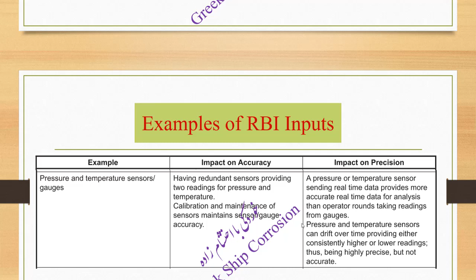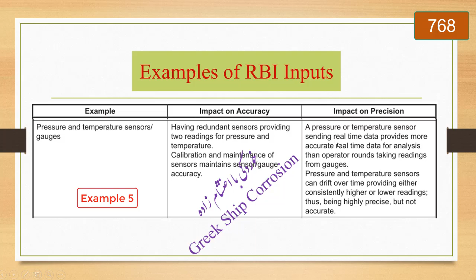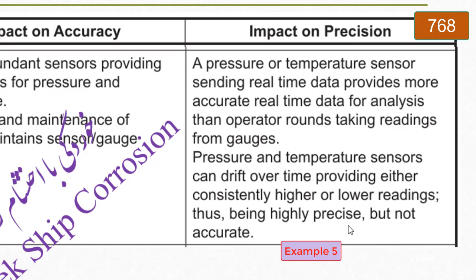Another example, pressure and temperature sensors and gauges. Having redundant sensors providing two readings for pressure and temperature, calibration and maintenance of sensors maintains sensor gauge accuracy. A pressure or temperature sensor sending real-time data provides more accurate real-time data for analysis than operator rounds taking readings from gauges. Pressure and temperature sensors can drift over time, providing either consistently higher or lower readings, thus being highly precise but not accurate.